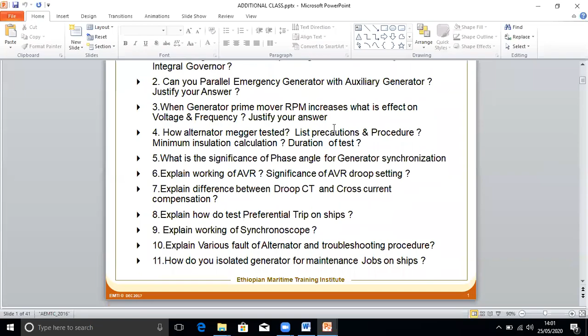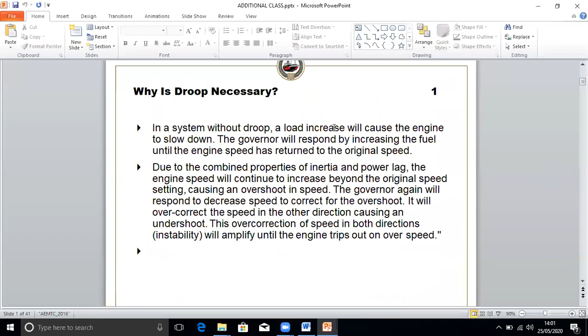First of all, we know why the droop is necessary. When running in parallel, you can observe the effect of droop when PMS is in manual. As you load the generator, you can see the speed drops. That is the droop. So a system without droop, the load increase will cause the engine to slow down.